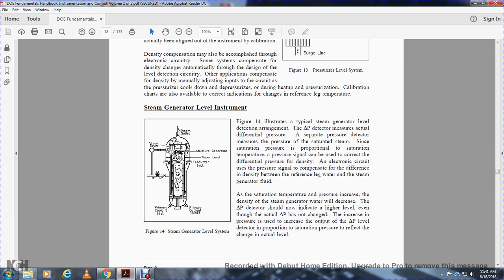As the saturation temperature of the pressure increases, the density of the water decreases with the differential pressure of the detector. This should indicate a higher level, even though the differential pressure has not changed. The increase of the pressure increases the output of the differential pressure of the level detector, proportionate to the saturation pressure, reflective of the actual level.